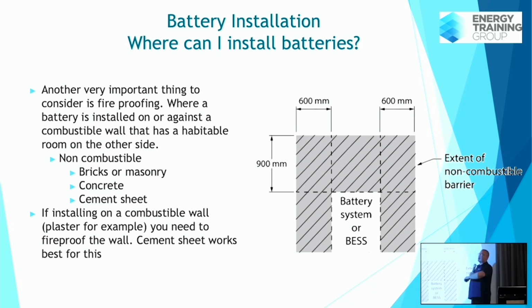You can hack the crap out of the wall and cover it up with cement sheet, so that's one advantage. However, that's only for a combustible wall. If you're installing on brick or cement, you don't have to worry about it. Even new weatherboard homes are fine, because weatherboard is actually a fire-rated material, but only if it's a new weatherboard home. Old weatherboards are just wood, not a fire-rated material, so it's a combustible surface and you'll need to fireproof the wall.